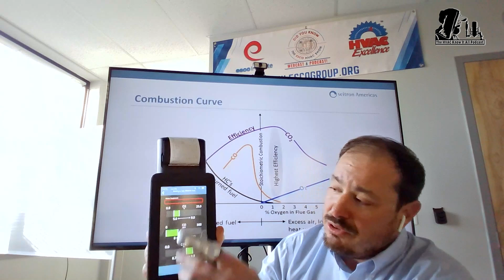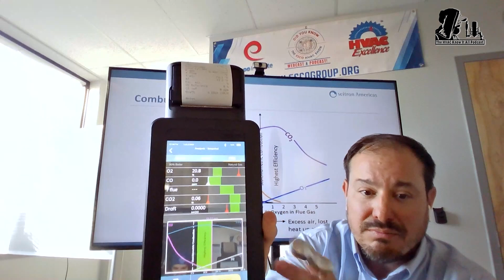So you can name the boiler or furnace, adjust your oxygen, CO, CO2 to their specs, name it, go back, and it'll always be there as part of your selection. Now if I go to, say, a 90% boiler and back to that screen, it'll show me where things stand once I start reading. Right now you're seeing a few things in red because we're not taking a measurement, but as long as we land in the green zone for all those parameters, you don't need to worry anymore. If you follow these specs, that boiler will run right.